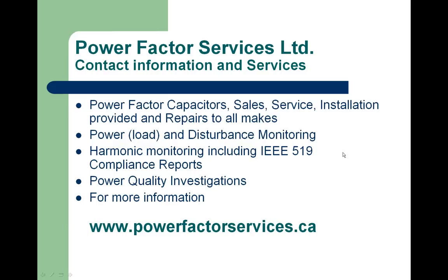Some transmission lines and local distribution feeders are more heavily loaded than before. The one thing I would say is that in most IT farms, large computer sites, the power factor is fairly high, and power factor correction is not even required. Even a computer is generally around unity. The only thing that reduces the power factor would be the air conditioning loads, and that sometimes could warrant putting in power factor correction if the savings were there. But I would always recommend a harmonic filtered bank for any loads that have sensitive equipment, and this is now even getting into CNC machines, etc.